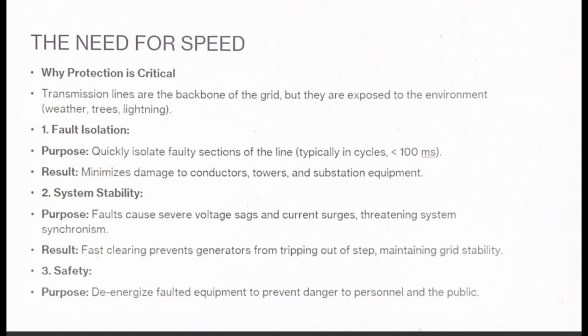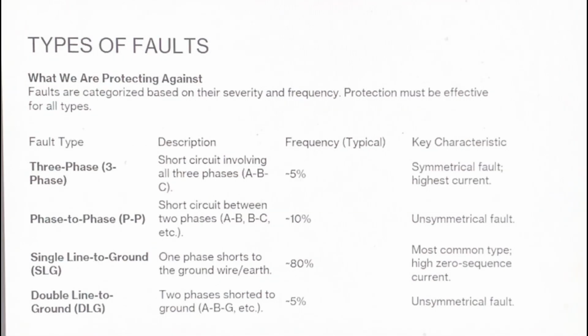Next is system stability. This is perhaps the most critical technical reason. A severe fault, especially one involving all three phases, acts like a huge drag on the entire electrical system. It causes severe voltage sags and current surges. If the fault isn't cleared instantly, generators across the system can lose synchronism, leading to cascading outages and widespread blackouts. Fast clearing maintains grid stability. So lastly is safety. Finally and most obviously, we must de-energize equipment to protect personnel and the public from hazardous voltage.